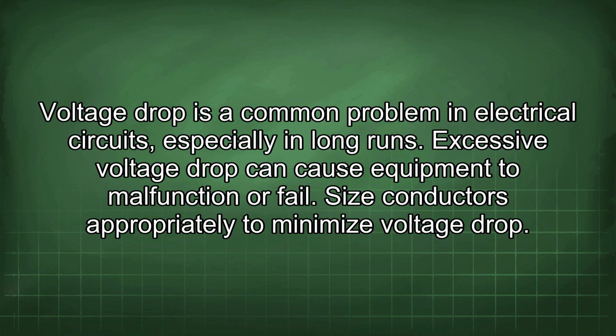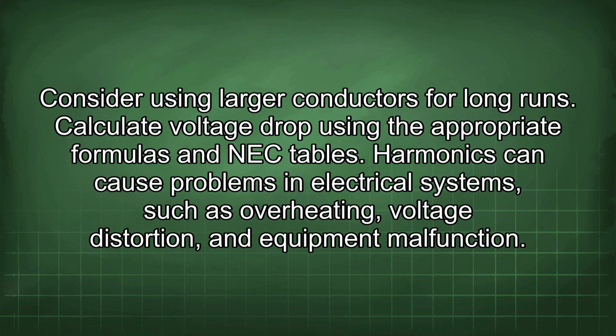Voltage drop is a common problem in electrical circuits, especially in long runs. Excessive voltage drop can cause equipment to malfunction or fail. Size conductors appropriately to minimize voltage drop. Consider using larger conductors for long runs. Calculate voltage drop using the appropriate formulas and NEC tables.